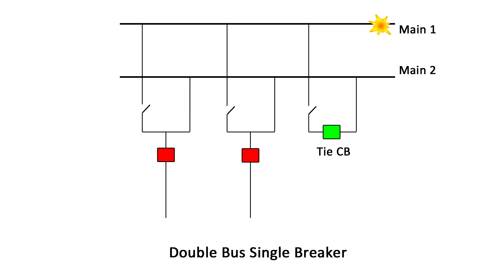The double bus, single breaker scheme is more expensive and requires more installation space than the single bus configuration. It is common to find this scheme with an additional transfer bus in transmission substations.